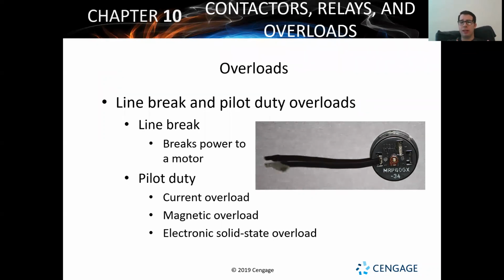So the line break's whole idea is we're going to have it where we can make sure we're not going to have a compressor or a component overheating or turning on when it shouldn't. And how are we going to stop it from turning on? Oh, how can we do that? What would be the solution? Well, just put this overload in series with the motor. Because if it's in series with the motor and it's open, then the motor is going to be treated as open and it's not going to turn on. And that's the whole idea behind a line break.